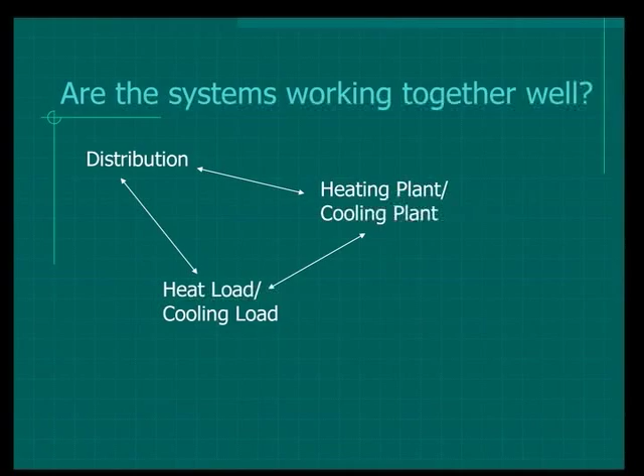If you've got a furnace that's larger than the ductwork, there's going to be inefficiencies and possibly noise on that furnace, or it's just not going to work right. John talked about how we measure external static pressure and heat rise. Those are two indications of whether the duct system matches the furnace.